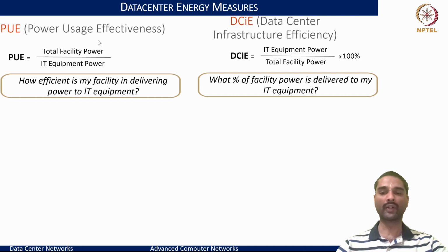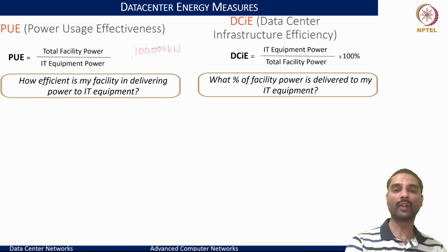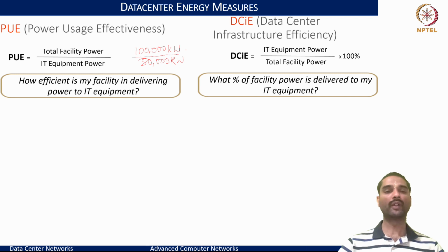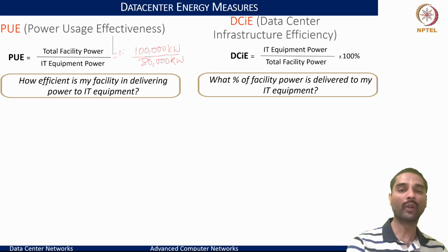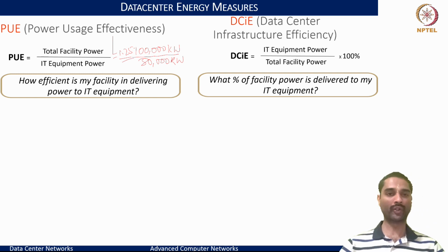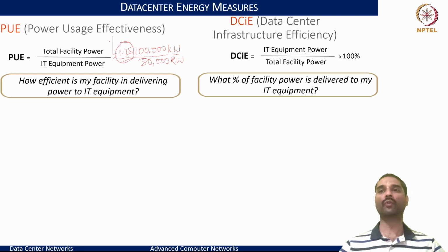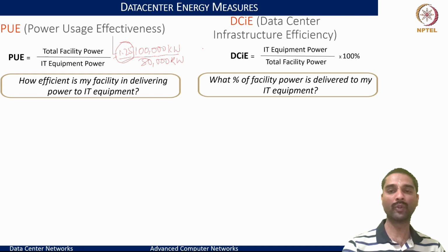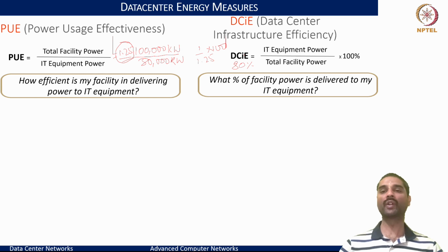For example, if a data center facility uses roughly 100,000 kilowatts as total facility power, and around 80,000 kilowatts is used to drive the IT equipment, then PUE equals 100,000 kilowatt divided by 80,000 kilowatt, translating to 1.25. So the PUE index for such a data center would be around 1.25. Likewise, DCiE would be 1 over 1.25 into 100, translating to 80% effectiveness in terms of how much total power has been delivered to the IT equipment.